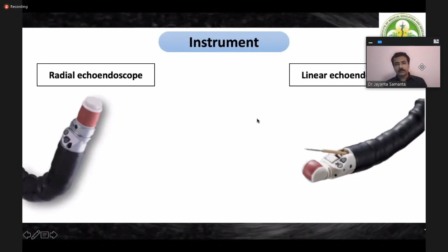These echoendoscopes are forward oblique view echoendoscopes, so it acts just like a side-viewing endoscope. The camera is on the side and the transducer is fitted at the tip, and it gives a 360 degree ultrasound scanning image. The depth of field is around 3 millimeters to 100 millimeters, and the working channel diameter is just 2.2 millimeters. I'd like to reiterate that the radial echoendoscope is primarily for diagnostic purposes only. It does not have any therapeutic purposes, and even FNA or FNB cannot be done with a radial echoendoscope.